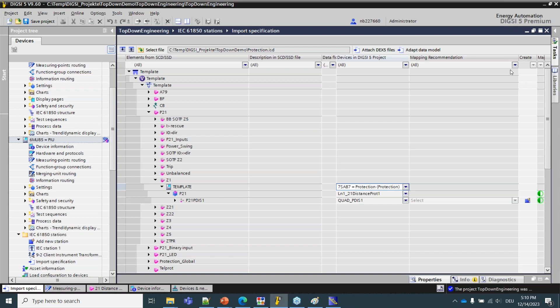Yes. Okay. Let's move on to the next step and the final step for me today, where we receive the feedback file from the IED manufacturer, the process ICD file just mentioned by Cedric. We will use the process ICD files provided by all the manufacturers in the substation and all the 61850 information contained in them to implement our specification. Finally, we will be able to generate an SCD file which contains the complete substation configuration, the control blocks, the datasets, the XREF, and all this that fits our specification and the IED manufacturer IED. This file can then be exported again to the manufacturer to be loaded in the IED itself.